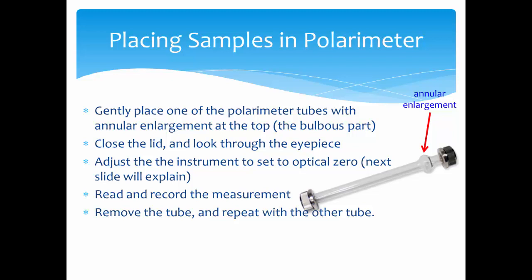Adjust the instrument to set to optical zero, which we'll explain in the next slide, and read and record the measurement. Remove the tube and repeat with the other tube.